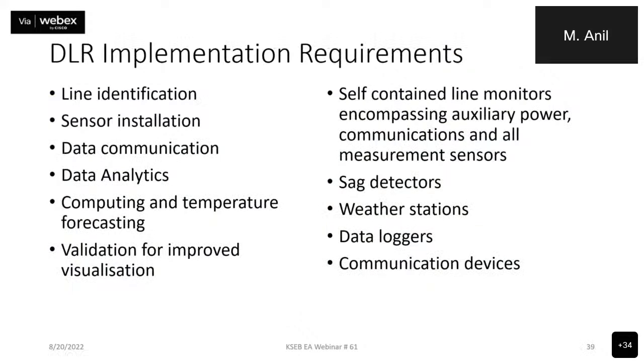DLR implementation requirements: line identification, sensor installations to sense the wind speed, wind direction, solar intensity, ambient temperature, etc. Data communication capability to communicate the data captured in real time to the system operator. Data analytics by means of software, that is how better we can load based upon the ambient conditions. Computing and temperature forecasting. Validation for improved visualization. Self-contained line monitors encompassing auxiliary power, communications, and all measurement sensors. Sag detectors, weather stations, data loggers, communication devices, etc.